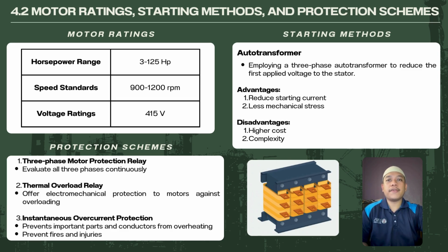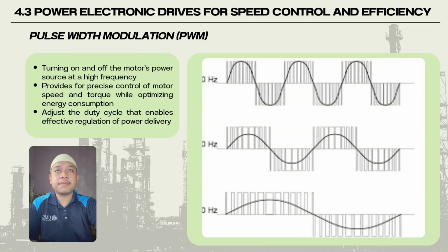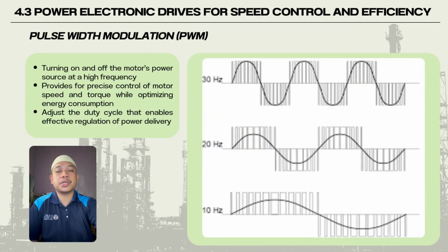Protection scheme. A 3-phase motor protection relay works to evaluate all 3 phases continuously to detect both phase disconnect and phase unbalanced conditions. Next, thermal overload relays are intended to offer electromechanical protection to motors against overloading caused by high input current from the main circuit. Last but not least, instantaneous overcurrent protection prevents important parts and conductors from overheating, which helps to prevent fire and injuries. And for my last part is the power electronic drive for speed control and efficiency.